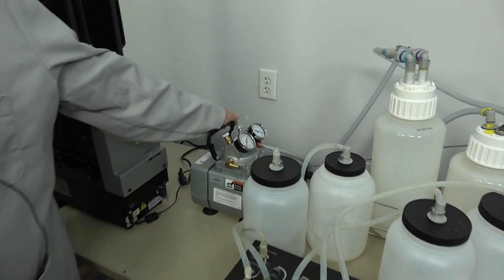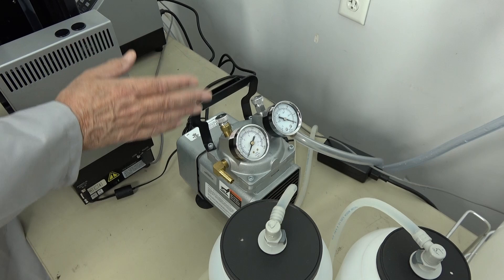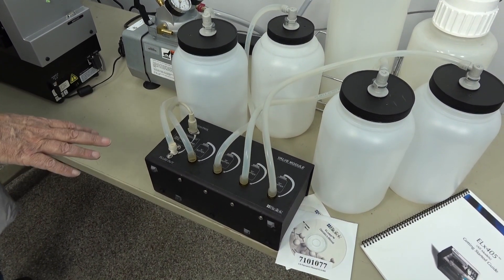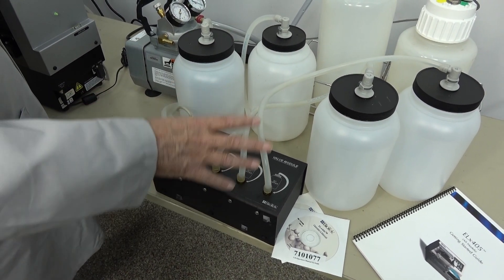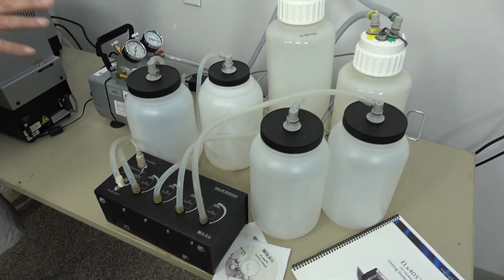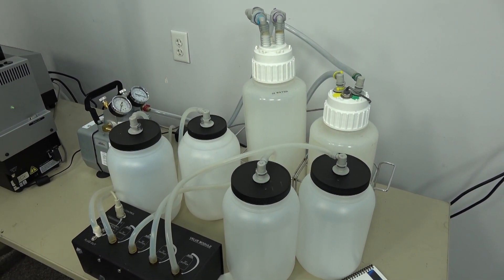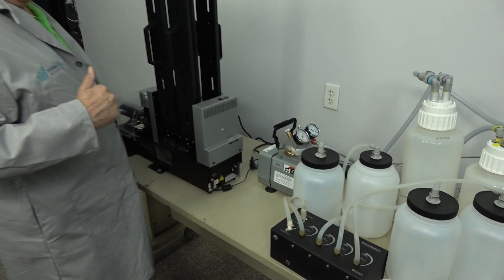Our offering will include a vacuum pump. Not everybody includes a vacuum pump. Sometimes we don't either. This one does. Another nice feature that this one has is the valve module, which allows you to have four reagent vessels connected at one time, and you're able to program your protocols to select which reagent you want to use.